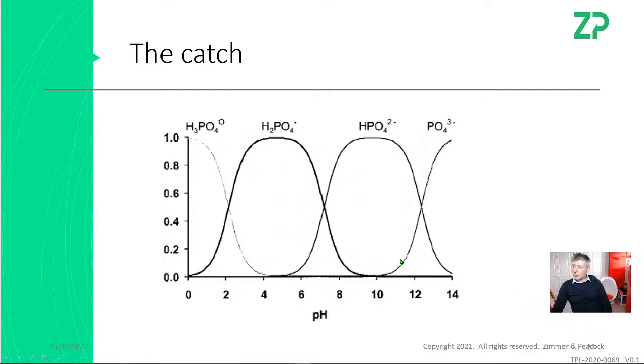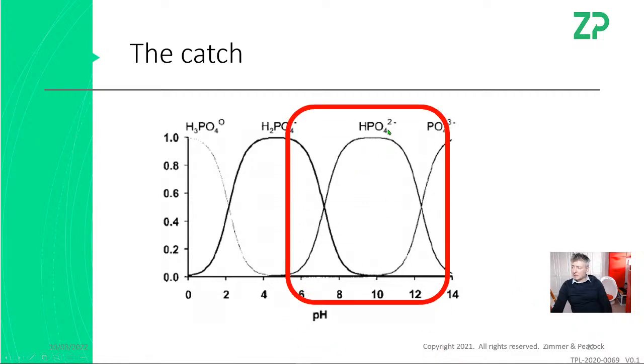Now the only thing about it is the phosphate sensor that we have is, phosphate has many speciations depending on the pH. So the phosphate that we are sensitive to is this monoprotonated phosphate here, which is the dominant species when you're working from something like pH 7 to around pH 12. Now I'm not suggesting that this user is anywhere near pH 12. They're probably in the range, I would guess, pH 6 to maybe pH 8. So it gives you a sense that this speciation changes, and this is the one we're sensitive to.